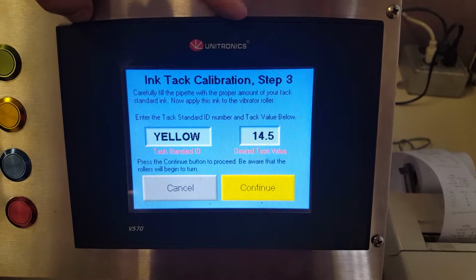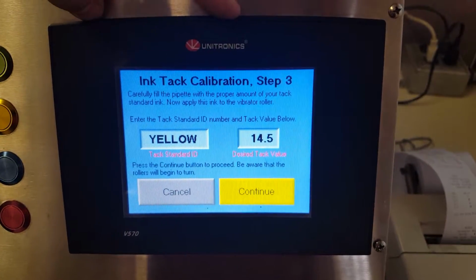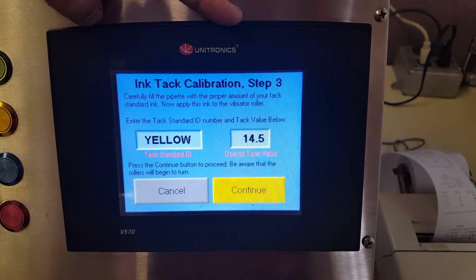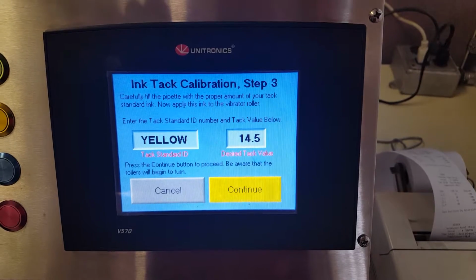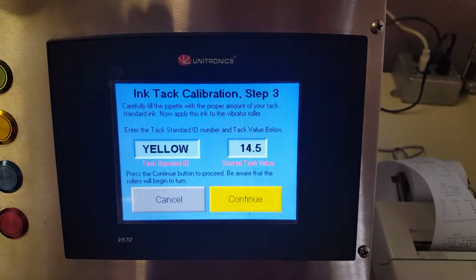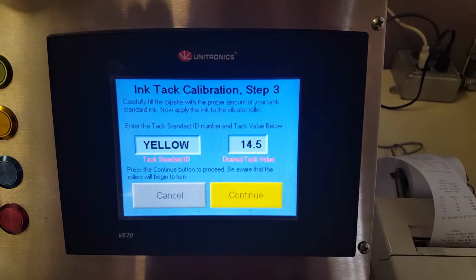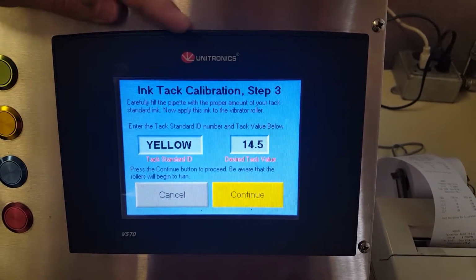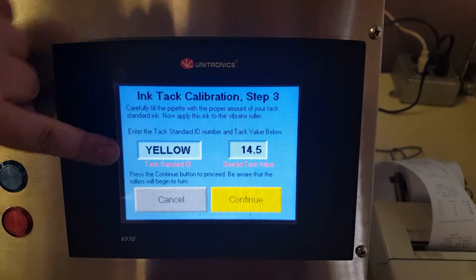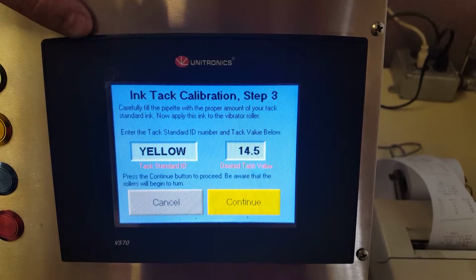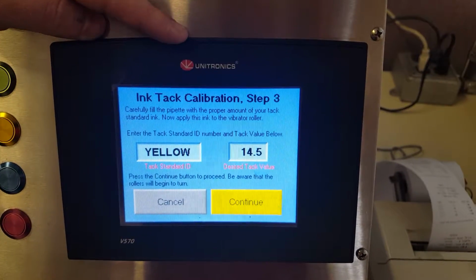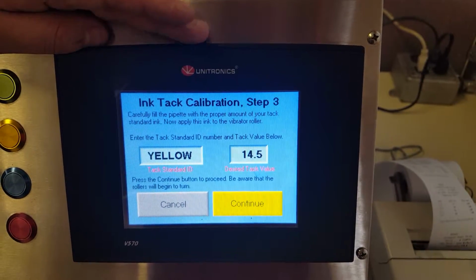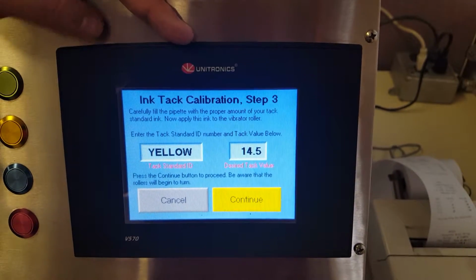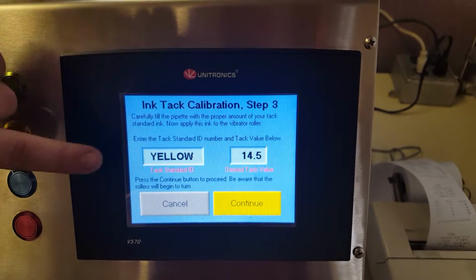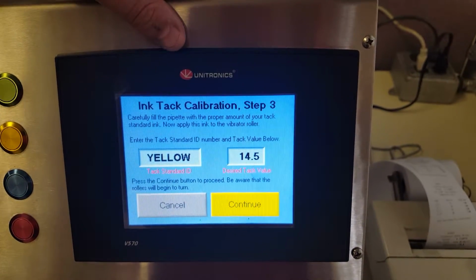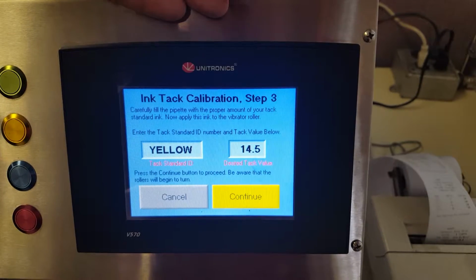Now, if you go through this calibration, or if one of your operators goes to run a test and the numbers come out different than they expected, they might be confused as to why, and if they want to find out which ink they used to calibrate this or where the parameter was established, they can go back into either the calibration screen or this one here, and you can key in an ID number and a tack number and so on. The calibration selection will be displayed on your printout as well. So if someone runs a test and the numbers are different, they'll be able to see the ID number, the number that was chosen, and whether they chose the dry or the ink tack calibration on your printout.